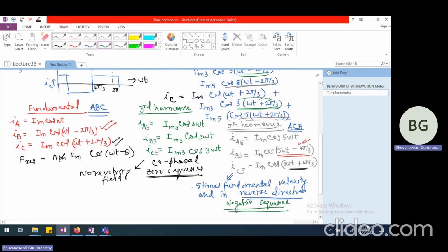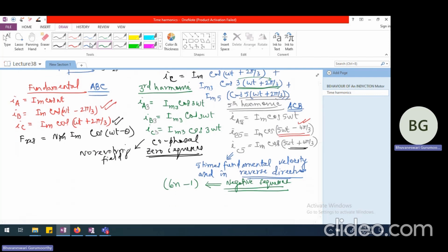In general, any 6n minus 1 harmonic, corresponding to n equal to 1, 2, 3, 4, and so on. For n equal to 1, it is the fifth harmonic. For n equal to 2, this corresponds to 12 minus 1, which is the 11th harmonic, and so on. All of these correspond to negative sequence, or reverse rotating magnetic field, but the speed will be 5 times in the fifth harmonic case.